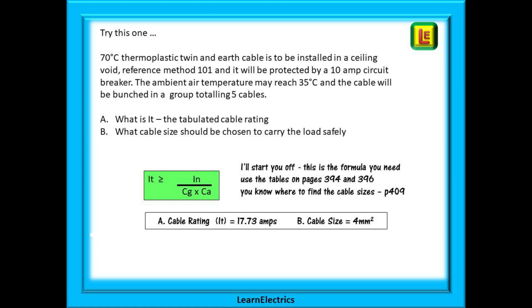And you should have cable rating IT is 17.73 amps and cable size is 4mm. Easy really. Just follow that simple logical process and break it down into small steps. It's no good trying to take shortcuts and doing the calculation all in one go if you get the wrong answer.